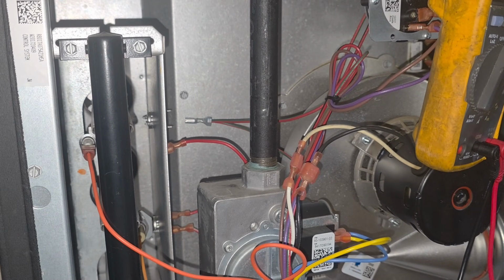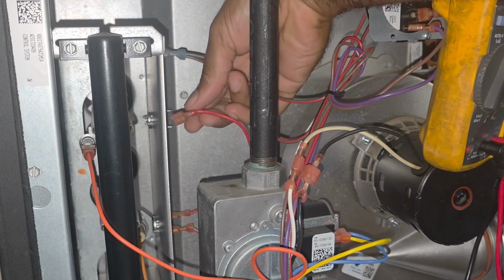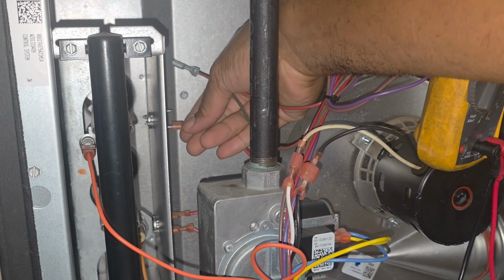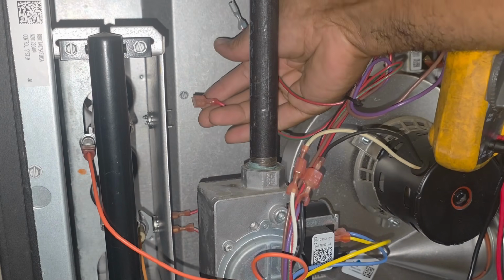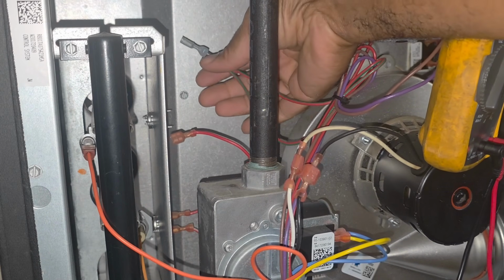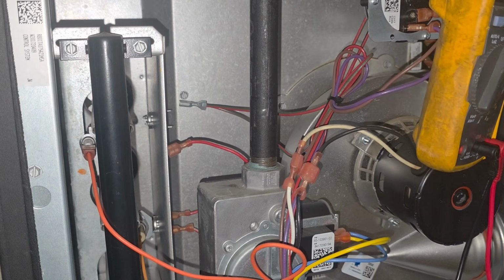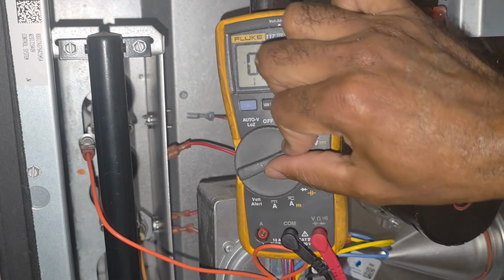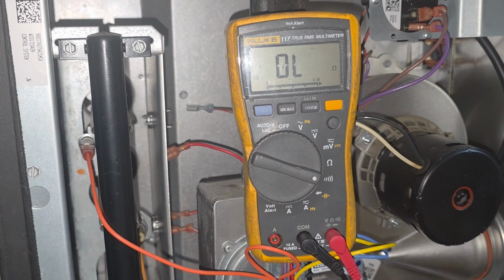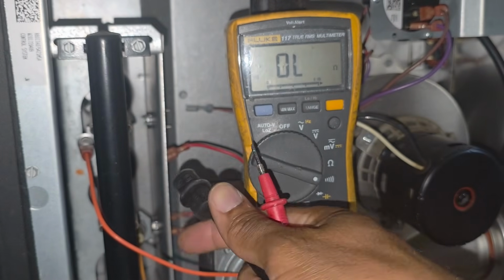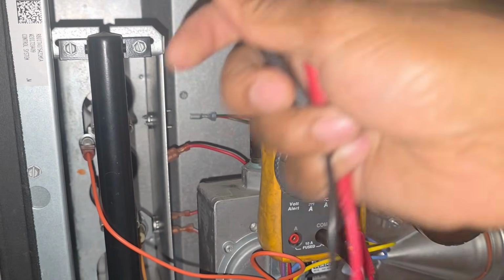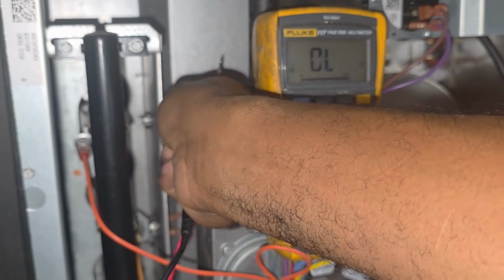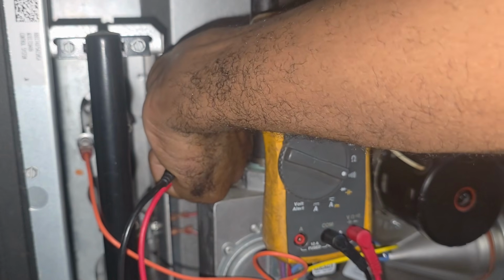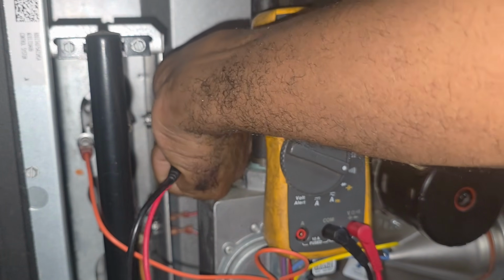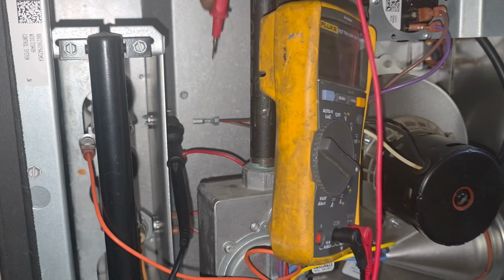All right, folks. So before somebody taught me this method, I don't know what the camera cut off here, but before somebody taught me this method, I would actually have to turn the unit off each time. I would take the leads off, and then I would get my meter and put it on continuity to see if that switch was open or closed. Now, and this is how you troubleshoot these switches also. If you did have an open limit, or when you was pivoting and you find out on three of them you had 24 volts on, but on the top fourth one you had zero.